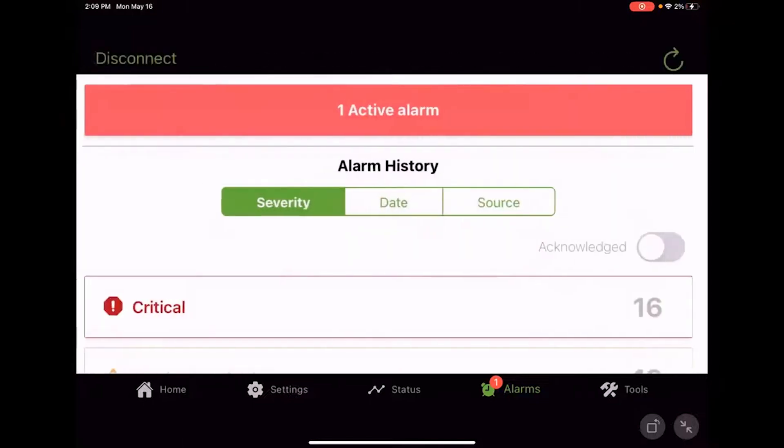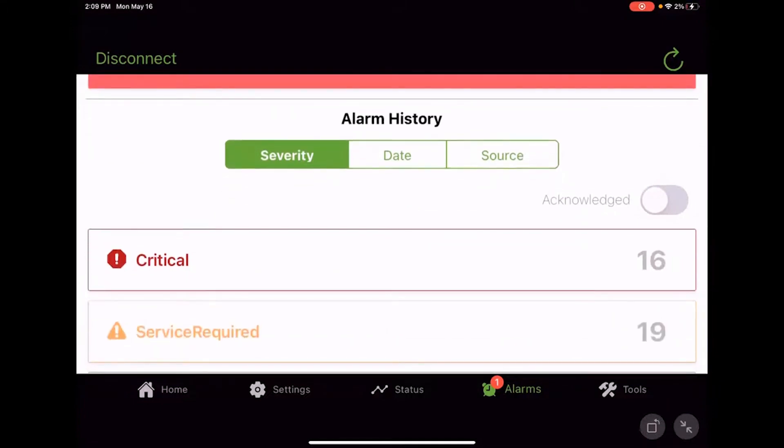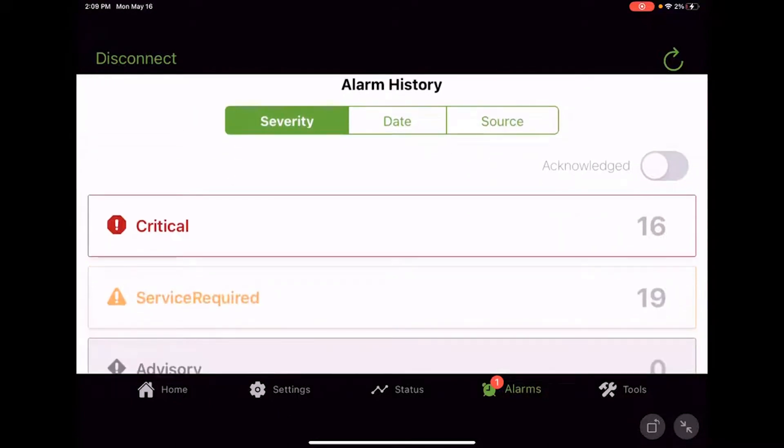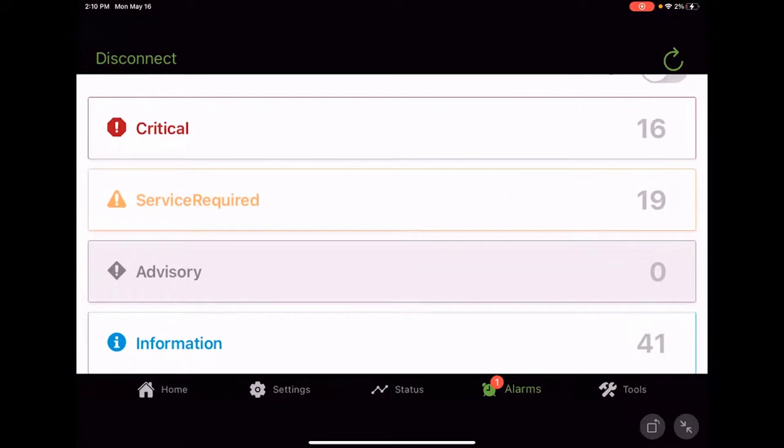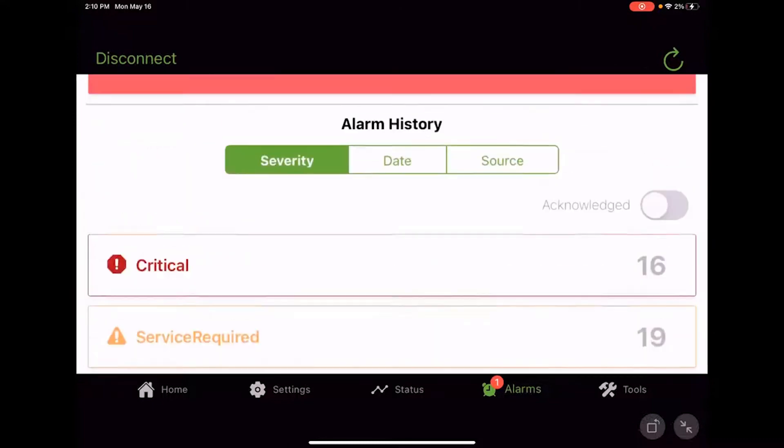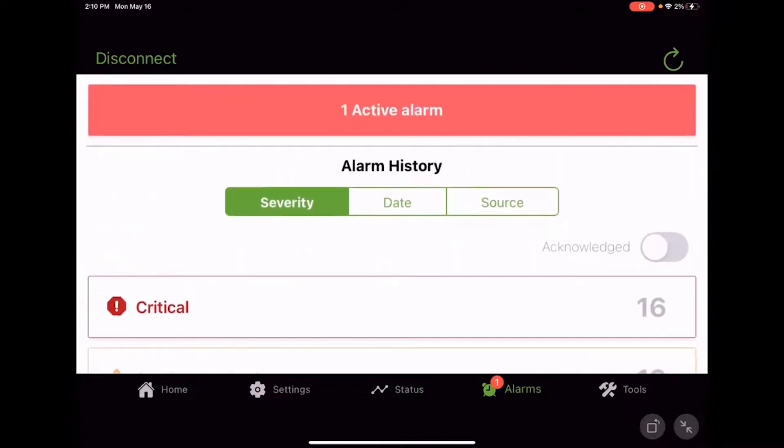Now, I've taken the unit out of BAS control, so hopefully we'll be able to reset that, but a little more on that in a bit. A couple other things we can do, we can actually sort our alarm history and see what's going on. And this unit, just so you know, I've actually power cycled and reset this controller several times today, making some of these videos. So it remembers some of those earlier alarms that I created and even some alarms from last week. So unlike some previous generation controls where if we cycle the power, we're going to lose the blink code, this controller is actually going to remember those alarms and give us some history.